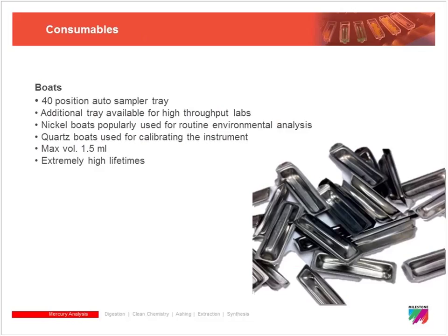So the samples are loaded onto the auto sampler tray. We offer two types of boats to contain your samples to load into the tray. The most common type of boat that we have is a nickel boat. So this is going to be perfect for your samples where you're analyzing any biological tissues or plant samples. The good thing about the nickel is they have a very, very high lifetime where they can be used over 2,000 times in the system and still maintain their complete integrity. We also offer the boats in quartz, and we generally only use the quartz for acidic or aqueous solutions. We also use them for calibrating the machine as well. But for all other types of applications, solids, soils, the nickel boats are what we recommend, and they also are very inexpensive. So if they do need to be replaced, there's not a huge cost associated with replacing the nickel boats.